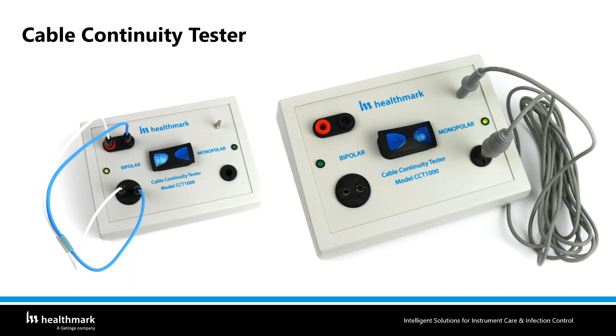So if this wire has any kind of high impedance, meaning there's breakage in the wire or the wires are not in good shape, it causes the light to not come on. So green is good, no green is bad. And here's the bipolar one that you can use with that. So any fault in any of these wires shows up. So that's basically a quick answer to the need that they have in SPD.